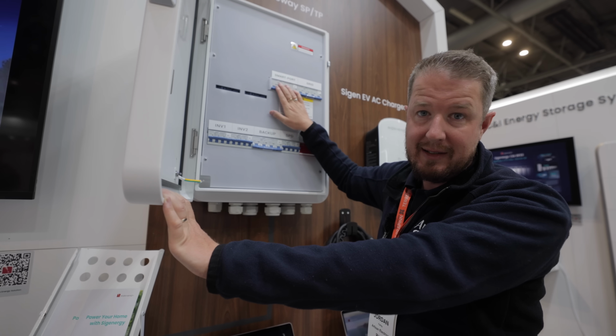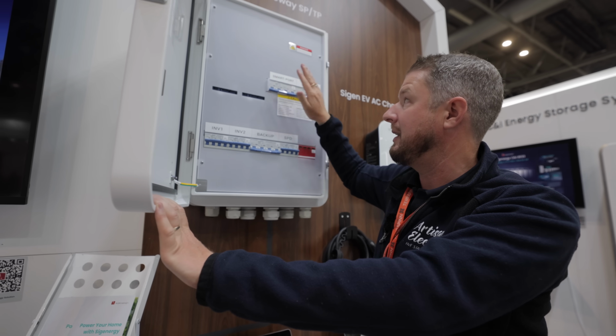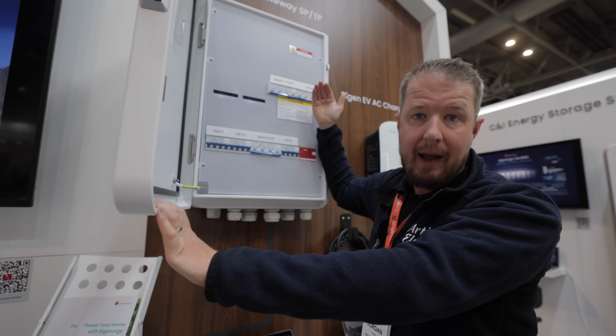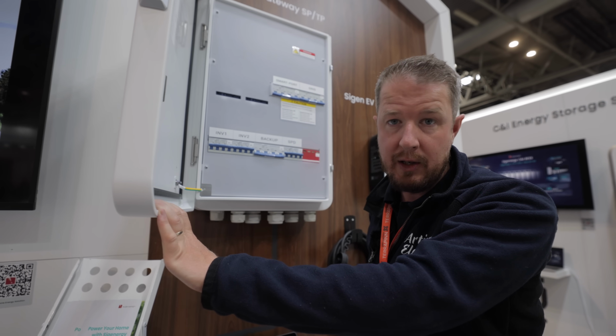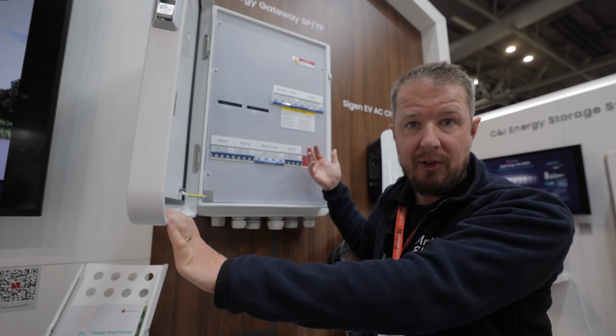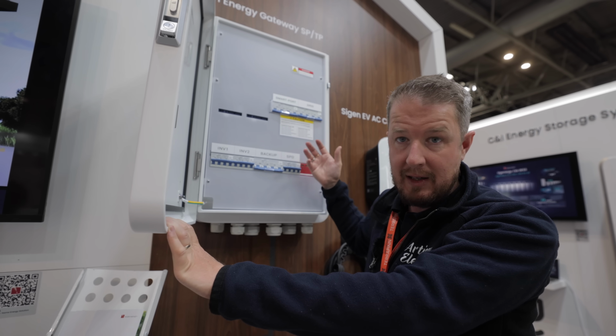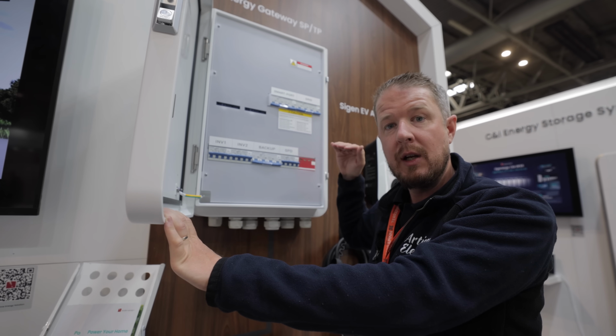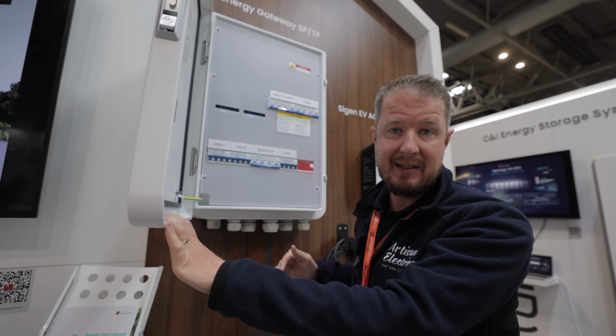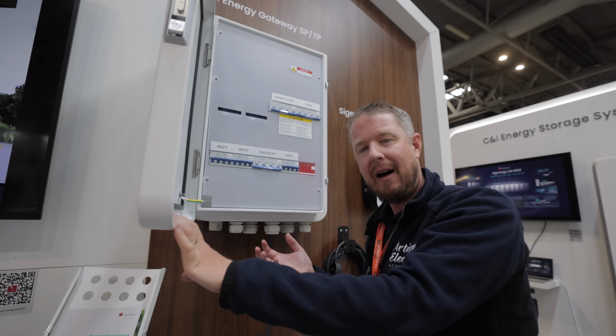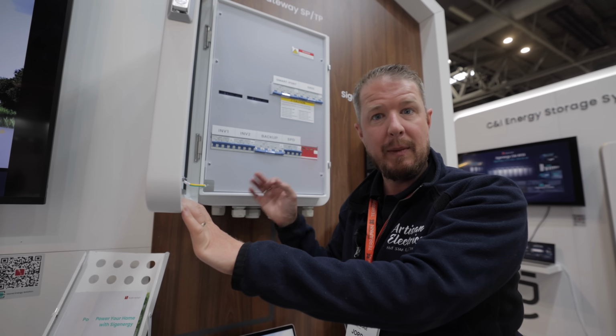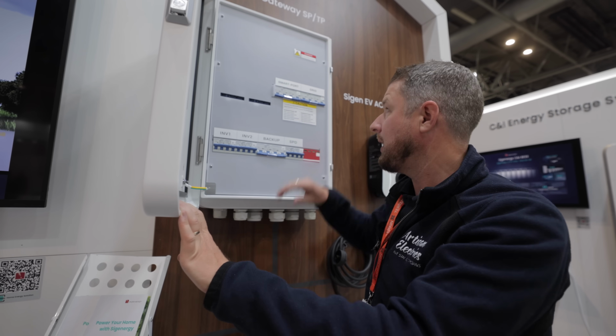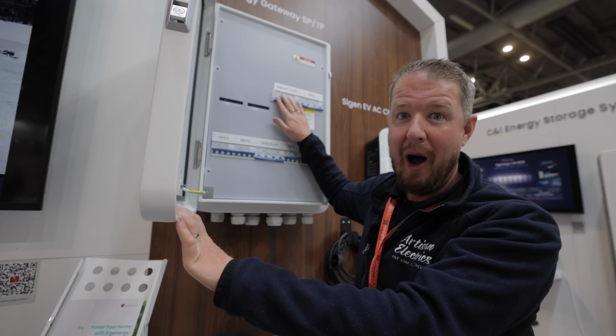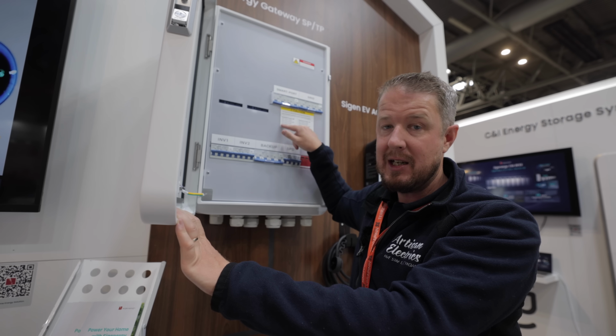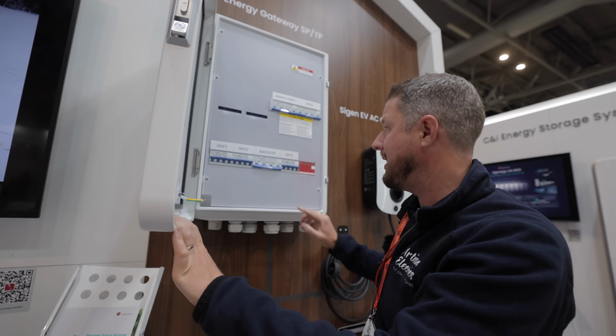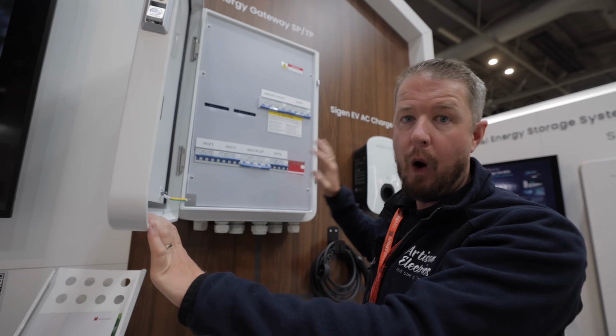The smart port also does other clever things, like allowing you to shut smart devices off during backup mode once the battery reaches a certain state of charge. So smart loads like a heat pump, or other devices that take a lot of power, can be shut off automatically at a certain state of charge - almost like having a non-backup side, but it's backup or non-backup depending on what you want and when. So just a heads up: if you're wiring a third-party inverter to a Sigenergy system, you need to wire it off the smart port, or before the gateway, and not on the backup side.